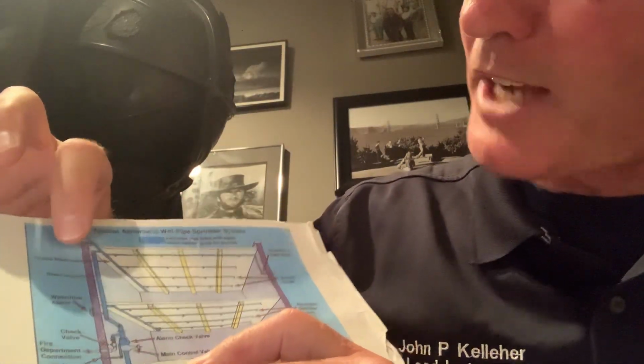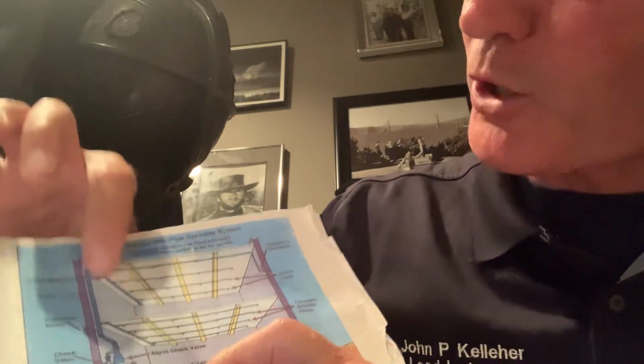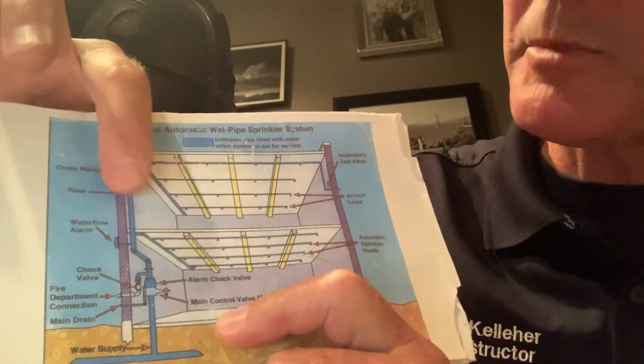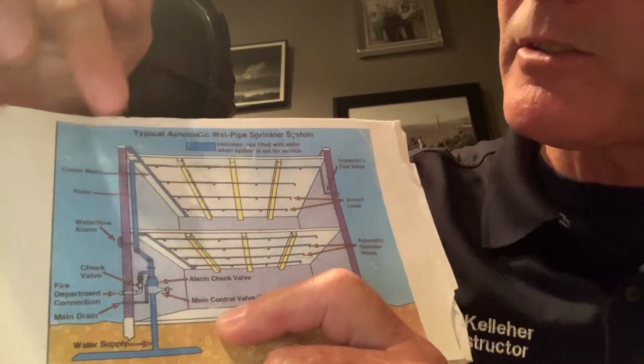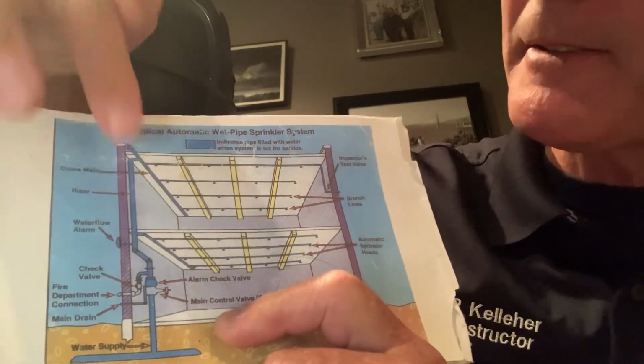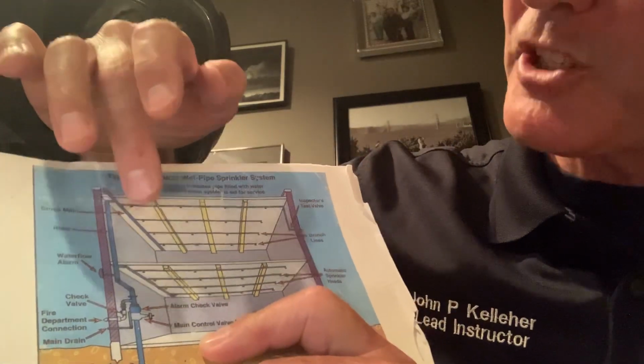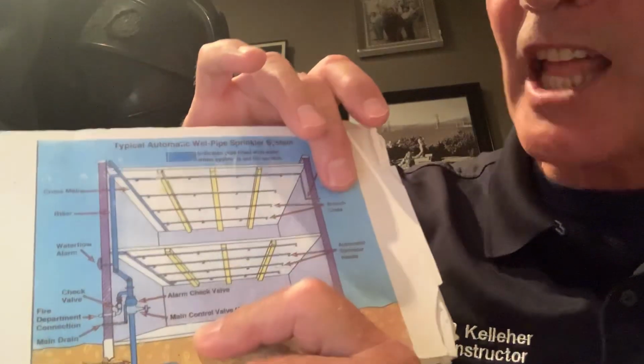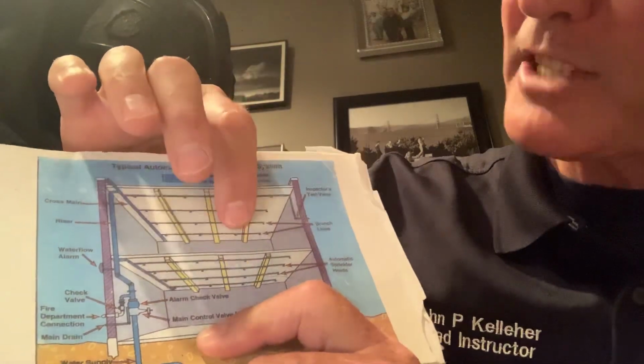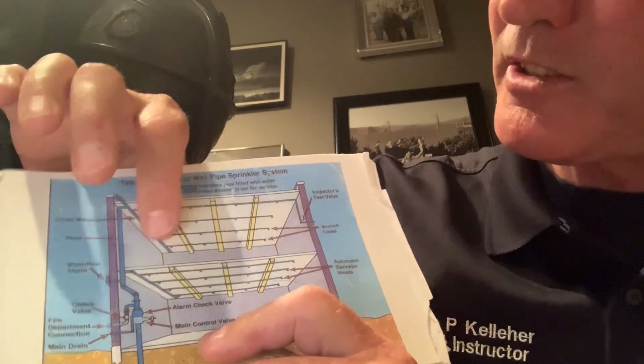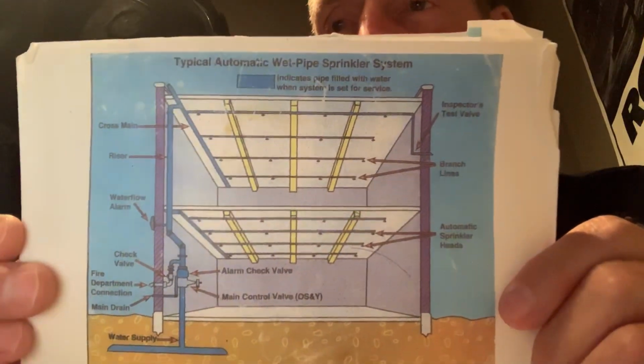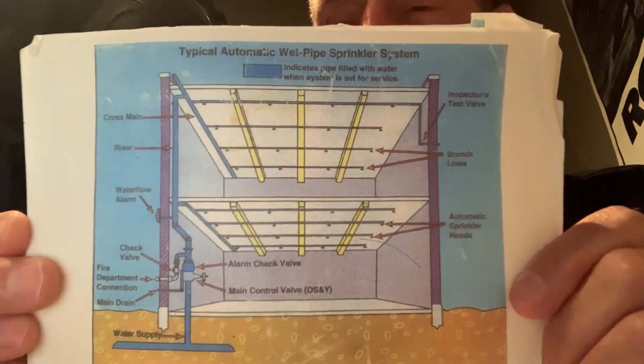Then as the water rises up the riser, it's going to branch off into what they call the cross main. Here's the cross main, running across like so. From the cross main, it branches off into the branch lines, which are right here. Off the branch lines are the sprinkler heads, these little dots. So that's your schematic of a typical wet pipe sprinkler system, okay?